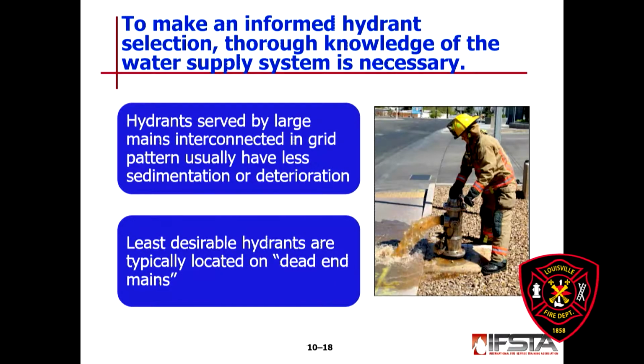Now, a couple things about dead-end mains. If you have done some planning, and you may potentially know how much water you can get out of that hydrant, it's not necessarily a bad thing to take a dead-end hydrant. It's water. If it's there, it's available. It's right there. One thing I would really stress, and I know we don't do this on most of our hydrants, but if you know it's a dead-end hydrant, I would flush that hydrant, or have your water guy flush that hydrant, prior to hooking that supply line up. You don't want all that nasty sediment and debris flowing through your pump if you can help it.